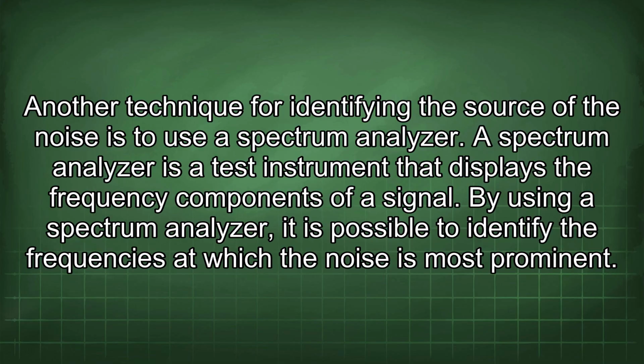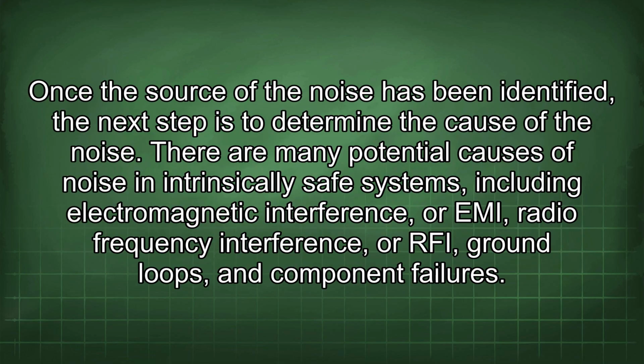A spectrum analyzer is a test instrument that displays the frequency components of a signal. By using a spectrum analyzer, it is possible to identify the frequencies at which the noise is most prominent. Once the source of the noise has been identified, the next step is to determine the cause of the noise. There are many potential causes of noise in intrinsically safe systems, including electromagnetic interference, or EMI, radio frequency interference or RFI, ground loops, and component failures.